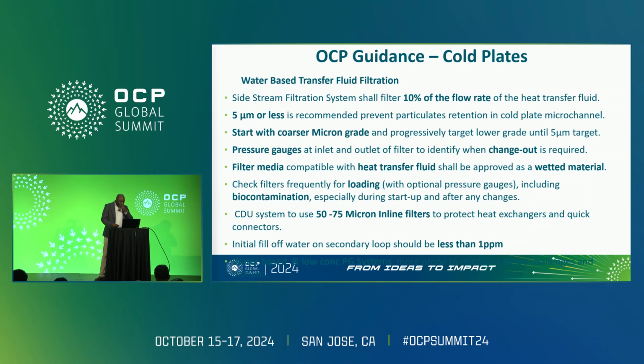Great presentation earlier by Keegan, Philip and Saha, who presented a good update on guidance, and I used their submission also, the reference to requirements. So touching on treated water, biocontamination is a big danger as identified by Philip. So watch out for biofilm formation, and in fact biofilm can even form on the filters themselves. You can mitigate against this by using zinc silver type microbial filters, but do watch out if you're using it in treated water. If the water has high resistivity, then you could have compatibility issues when using these microbial type filters.